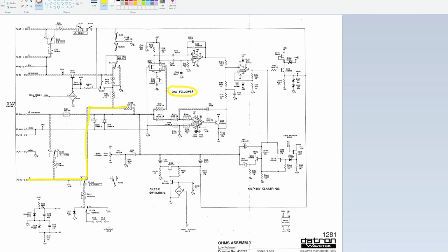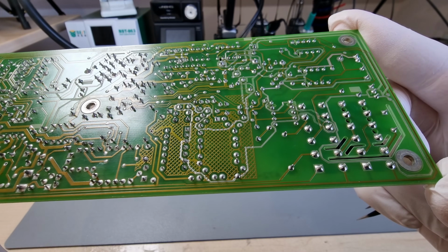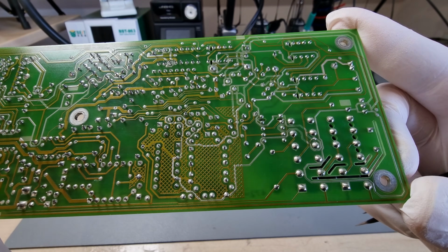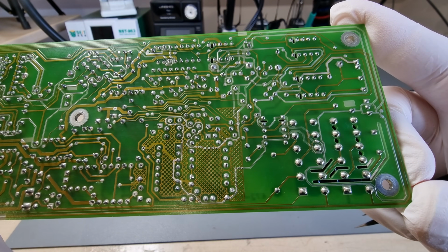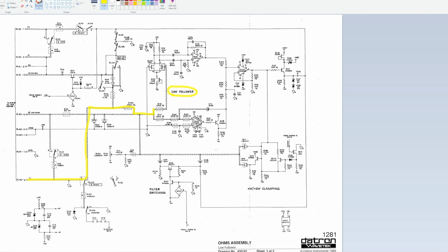Depending on substrate and cleanliness, such a low current can easily be overshadowed by surface or interlayer leakage currents, which is why this node and everything associated with it is surrounded by an exposed guard ring on the PCB. The signal on this guard ring is just a local ground, I think, because I- is expected to be around 0 volt. There seems to be a little bit of optional analog filtering. With these two relays, this entire carefully designed circuit can be shown the middle finger, and it can be configured for 2-wire measurements.